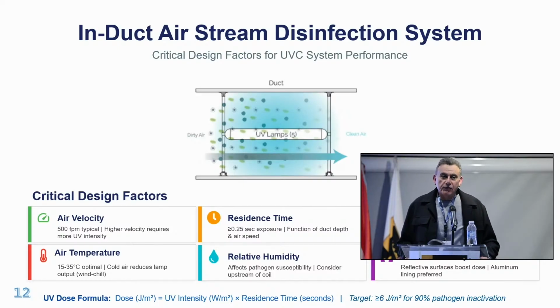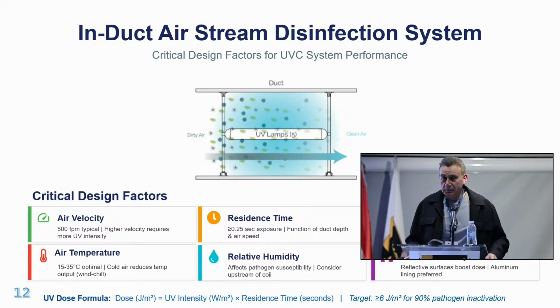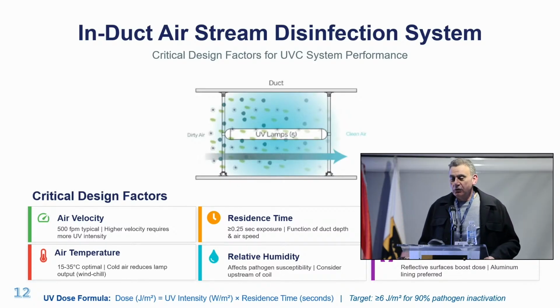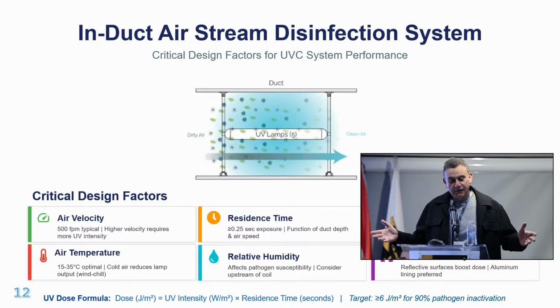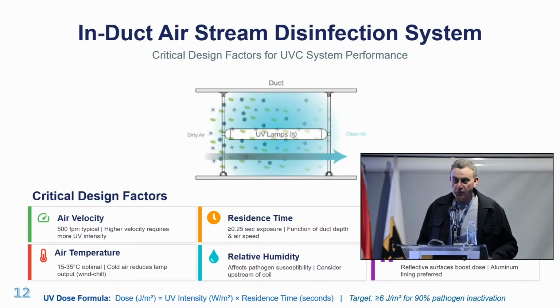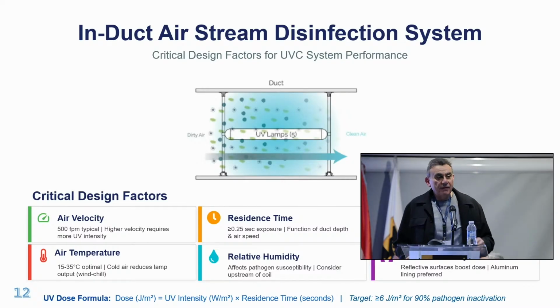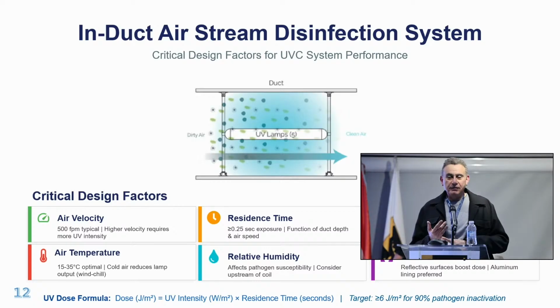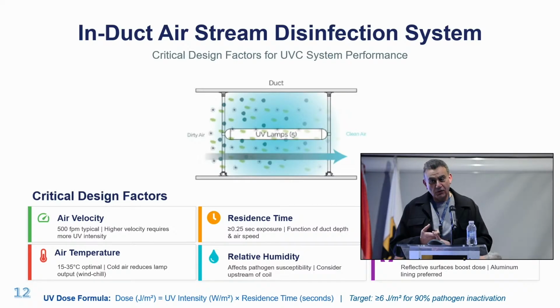The other important thing also is the type of plenum. You can use a galvanized steel plenum. It has a reflectance, which is okay. The best one to use is a stainless steel plenum because it reflects the light very well. What you do not want to use is a plenum that's internally lined with a black lining, because that's also a waste of money. No reflectance whatsoever of the light. So these are the important things: the direction of the light, the air velocity, reflectivity of the light, and the intensity, of course, of the UV light.